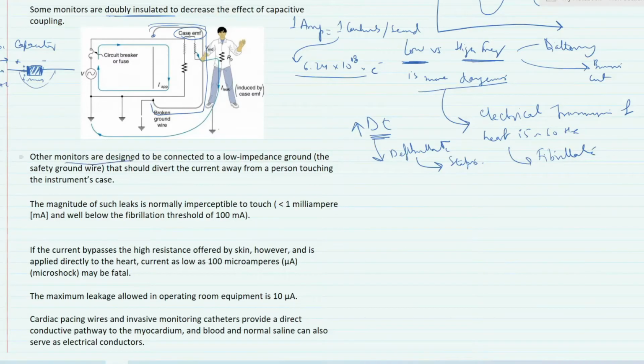Other monitors are designed to be connected to a low impedance ground - the safety ground wire, which we've already discussed. That should divert the current away from the person touching the instrument's case, because current always flows through the path of least resistance.